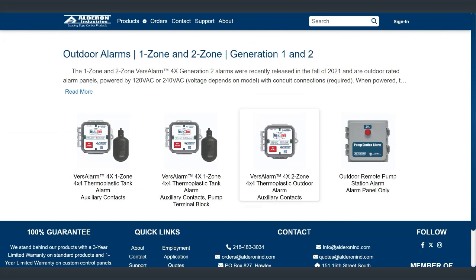Brought a sample with, and I'll take it out of the box, just so I can pass around this other one too. So our VersAlarm 4X is 4X rated. Everything's enclosed. We have a buzzer on the side. Capacitive touch for silence. LEDs light up on the outside. Green when you have power to the unit and the system is normal. And if somebody doesn't like those green LED indicators, you can actually turn that off. Just hold down the test silence button for like 30 seconds. And then it'll flash at you and it'll turn off.